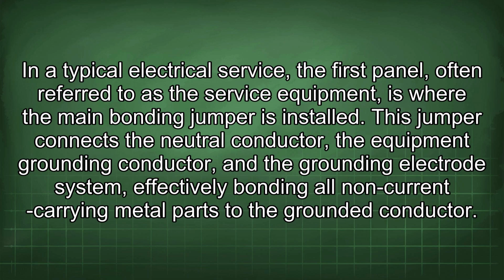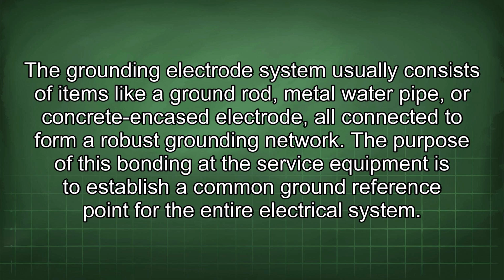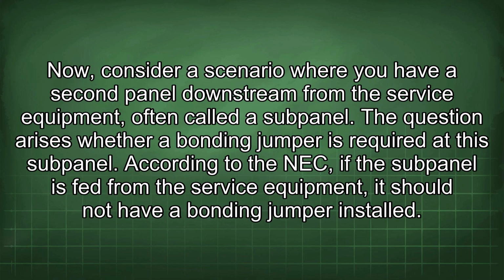In a typical electrical service, the first panel, often referred to as the service equipment, is where the main bonding jumper is installed. This jumper connects the neutral conductor, the equipment grounding conductor, and the grounding electrode system, effectively bonding all non-current carrying metal parts to the grounded conductor. The grounding electrode system usually consists of items like a ground rod, metal water pipe, or concrete encased electrode, all connected to form a robust grounding network. The purpose of this bonding at the service equipment is to establish a common ground reference point for the entire electrical system.